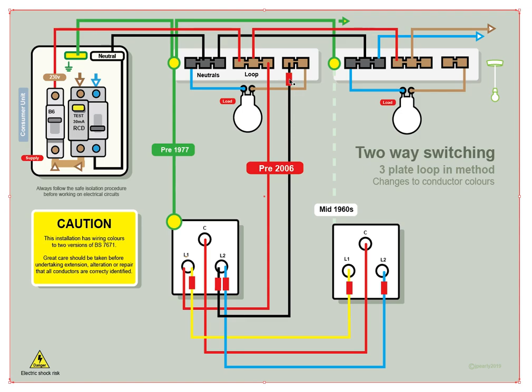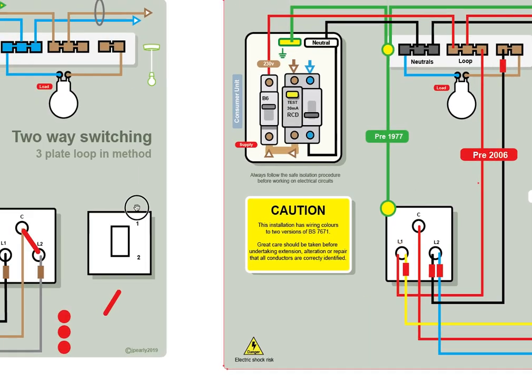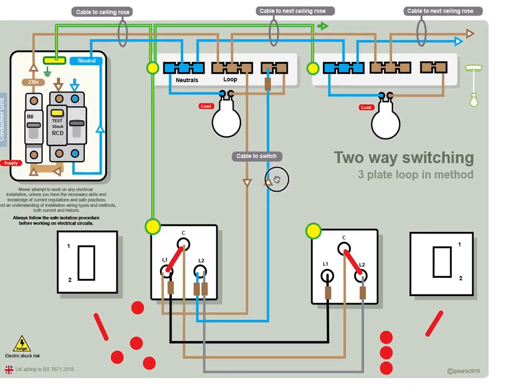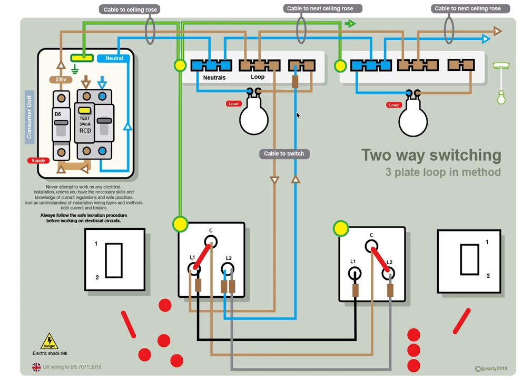So it's very important that you do identify what the conductor does. Just because the cable's black or blue doesn't mean it's a neutral. As you see, this one's been sleeved. We'll go back to the previous illustration. This is a blue cable, but it's not neutral, it's a switch cable, it's a live cable. And it's noted, it's indicated with some sleeving, brown sleeving at the ceiling rose and at the switch, to indicate that this is a conductor which is live, a line conductor, it's carrying 230 volts.